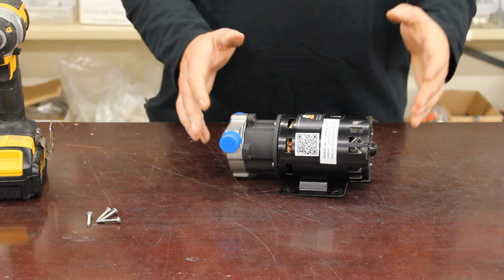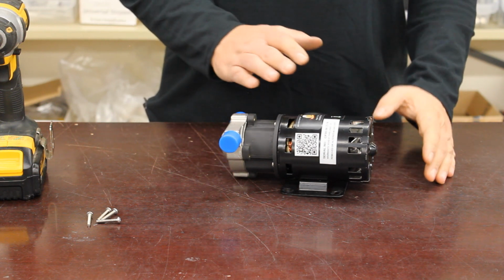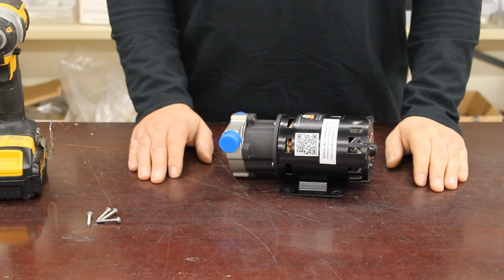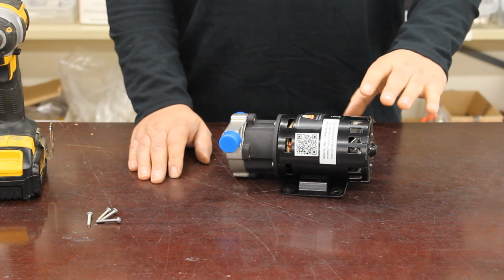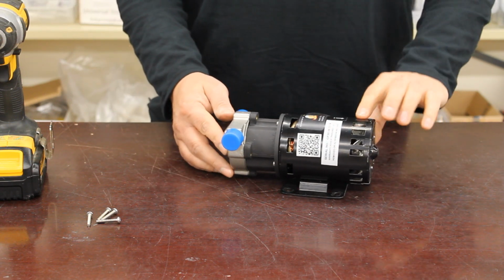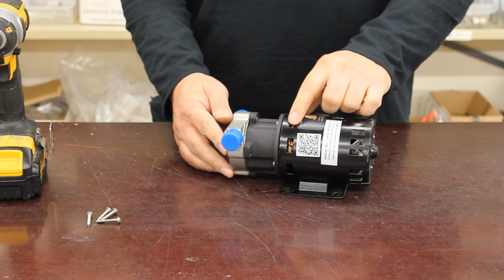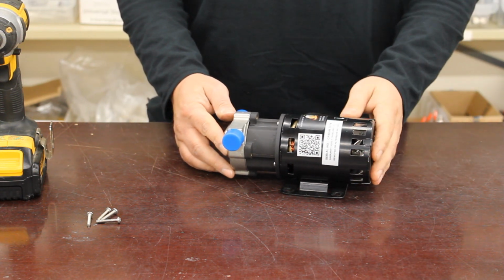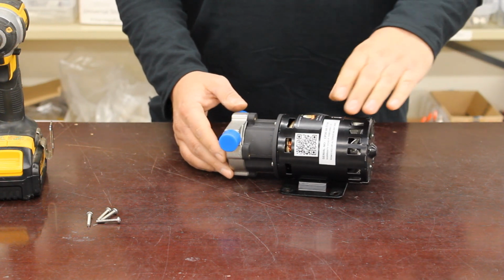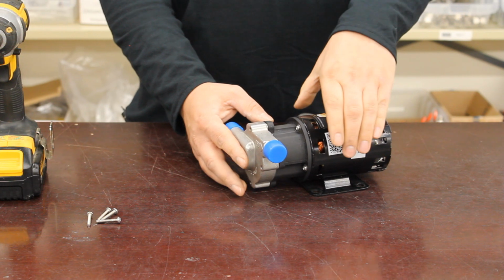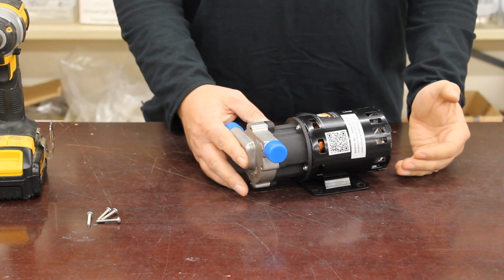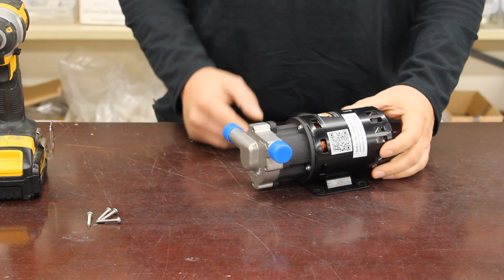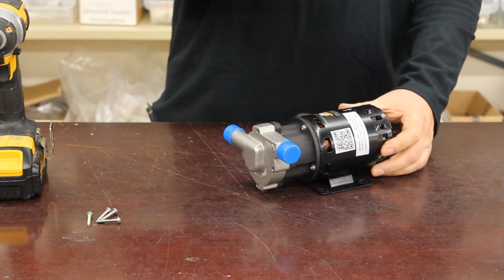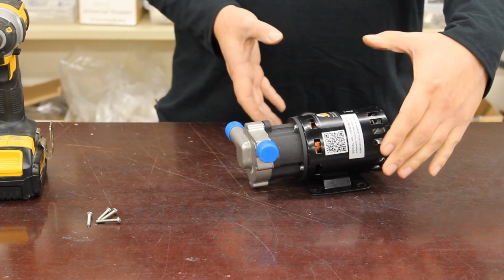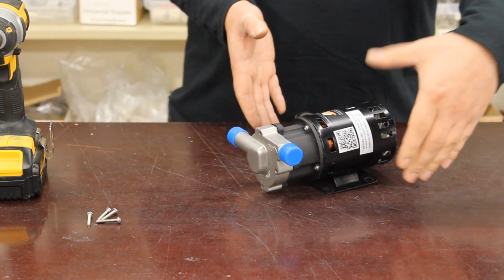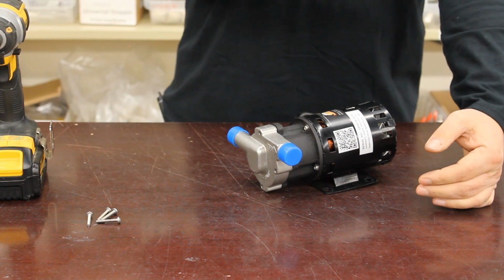Now, another reason why these pumps will overheat is because customers install shrouds over these, or like splash guards, and these motors use the cooling fan in the back here and the vent holes in the pump body to provide cooling for the motor coils, and you cannot really restrict the airspace around these pumps because it can't vent the heat fast enough. So if you're going to do any kind of shrouding for these pumps, just make sure that the clearance between that shroud and the pump motor is like 5-6 inches out like that, and that the top is well over the pump.